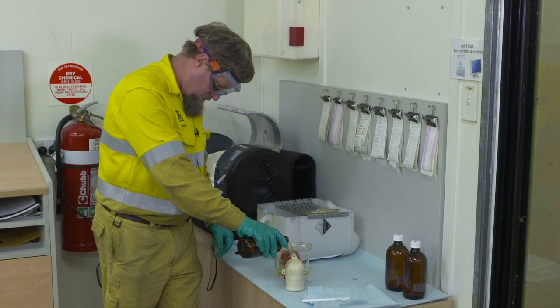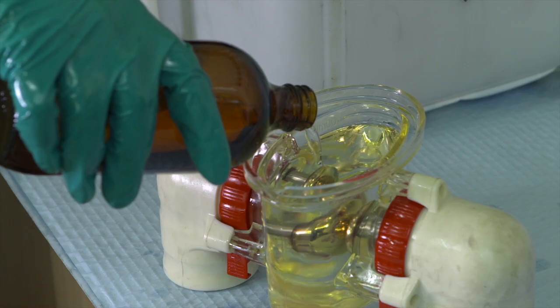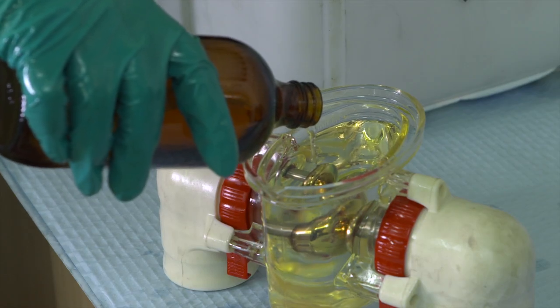It could be caused by an air bubble that floats down between the electrodes during the test. It could be caused by a bit of contamination on the electrodes, or maybe even general contamination that floats down between the electrodes while the test is being undertaken. If you do get a dodgy sample, discard what you've got at the moment, take another sample and retest.